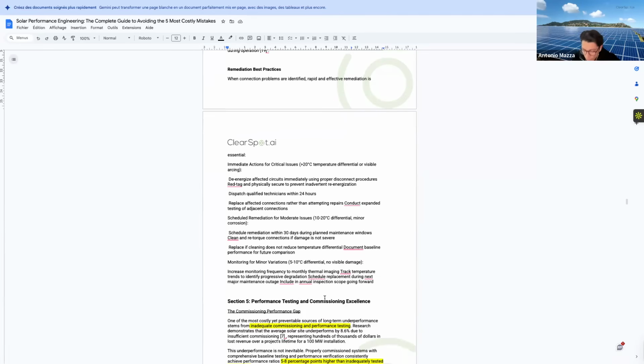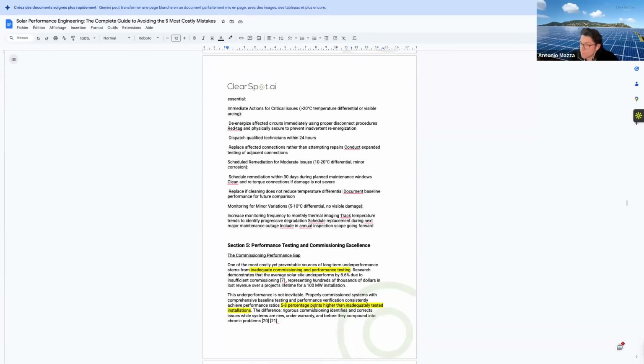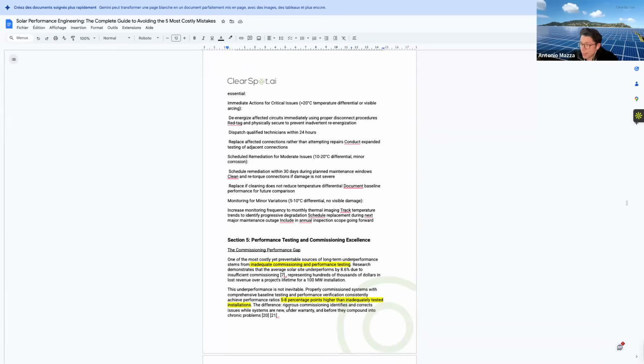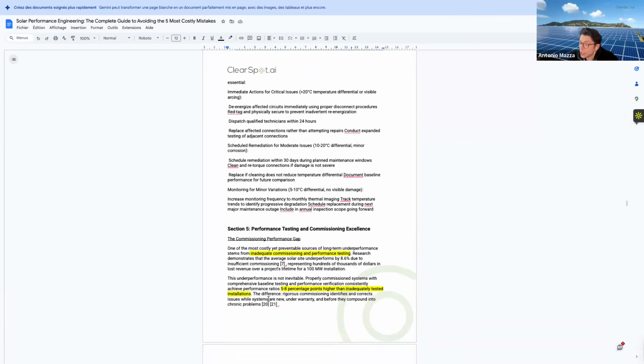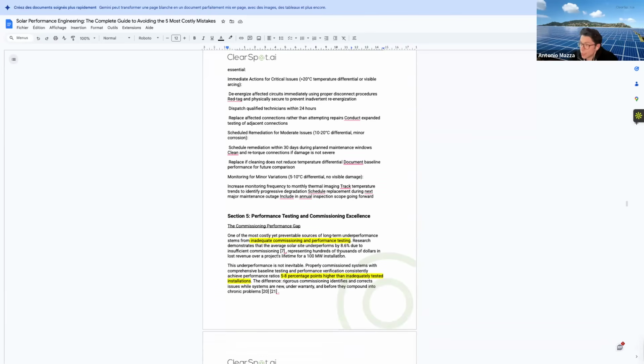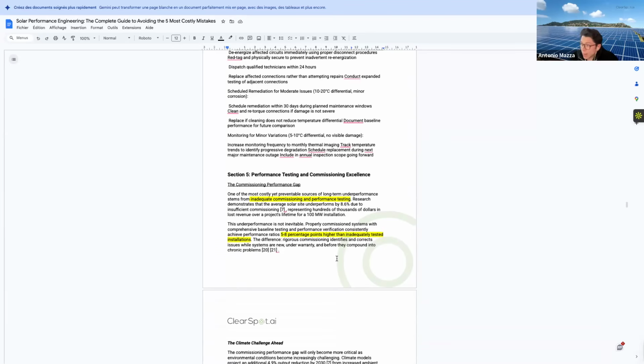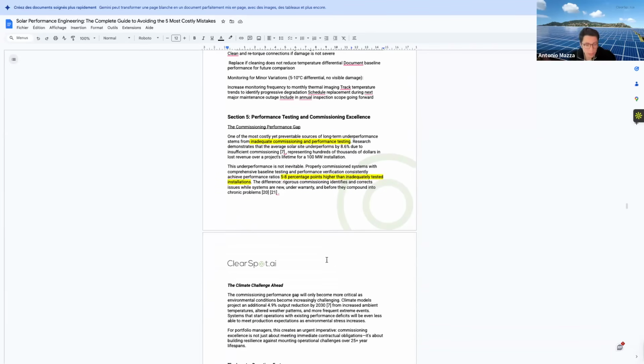Performance test. We had this, I think, last episode; we talk a lot about performance and all the indicators. One of the most costly yet preventable sources of long-term underperformance is inadequate commissioning and performance testing. Performance is 9.8 percentage points higher than inadequately tested installations. It's quite high: 8.6% lost due to insufficient commissioning, representing hundreds of thousands of dollars in lost revenue over the project lifetime for a 100 megawatt installation.